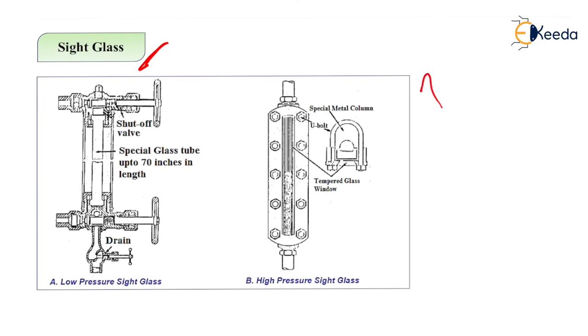The next direct measurement system is the sight glass. The diagram shows two types: low-pressure sight glass (type A) and high-pressure sight glass (type B). The level in the glass seeks the same position as the level in the tank, providing continuous visual indication of the liquid level in the process vessel or small tank. These are more convenient than dipstick and manual gauging tips. Sight glass A is more suitable for gauging in an open tank.